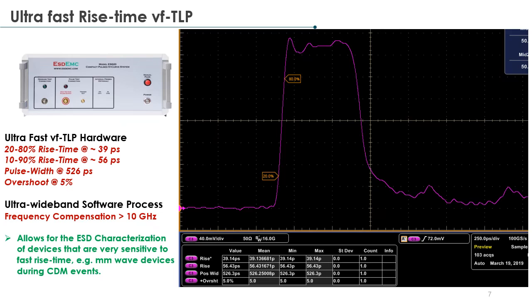Here's a waveform of our VFTLP's fastest pulse. This is our claimed 50 picoseconds rise time, which is actually less than that if you use the 20 to 80 rise time definition. Overshoot here is only 5%, even with a fast rise time like this and a short pulse width, this being just over a half a nanosecond pulse width in this case.